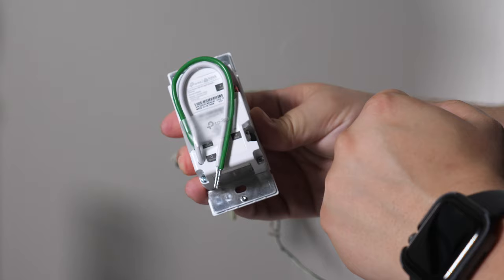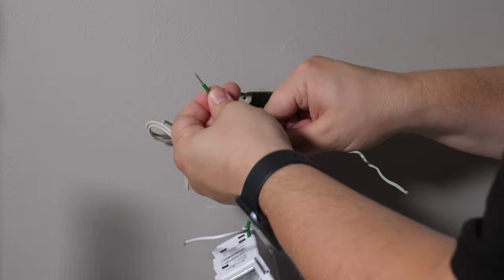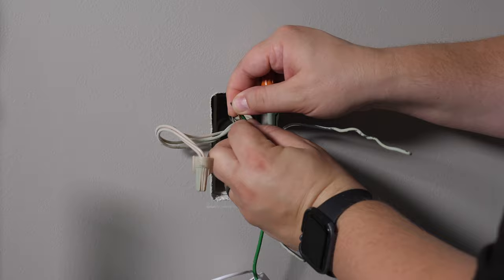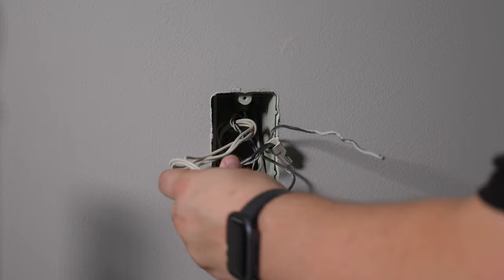First, let's go ahead and make the ground connection. All we have to do is put these two wires together. This is a green wire on this light switch, but in the box it's typically just a bare wire, which is your ground. We'll just put these two wires together as close as we can, and then we'll put this wire nut on and twist it out, and that will make this connection. I always like to pull on the nut just to make sure it's tight.